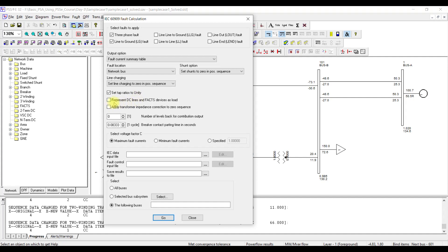I am going to uncheck 'represent DC lines' because we do not have DC lines and we usually do not consider them in short circuit analysis. I am also going to uncheck 'apply transformer impedance correction to zero sequence' — I do not want any correction applied to my reactance value. I want to use the actual reactance value for both the positive sequence and the zero sequence.